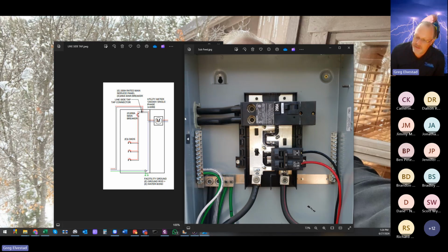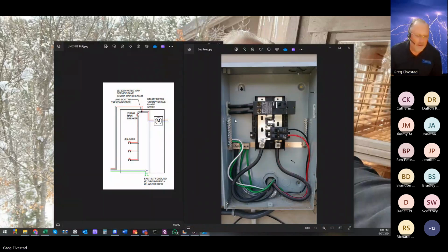The meter is adjacent to the left here behind this dead front. You have your distribution center, just like this one here. The meter, a dead front, a distribution center. Some people have been tempted to tap these wires here. Please don't do that. You're violating the listing of the panel by intercepting those wires and trying to connect solar on there with a fuse disconnect. These were never intended for them to be tapped.